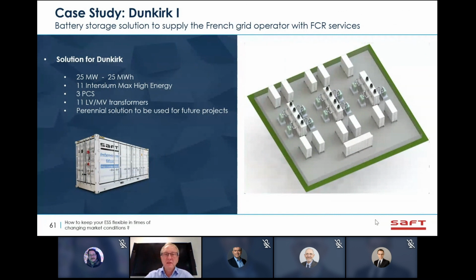This solution is built with 11 containers in Intensium Max High Energy, each providing 2.5 megawatt hours of storage capacity. These are connected to 3 groups of PCS, each with 3 or 4 low voltage, medium voltage transformers. So you can see here this basic arrangement of 3 or 4 containers, PCS and transformers will be the building block replicated on all future ESS systems Total will install in the frame of their contract with RTE.